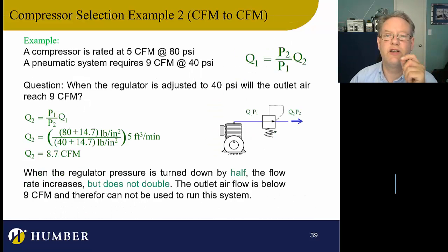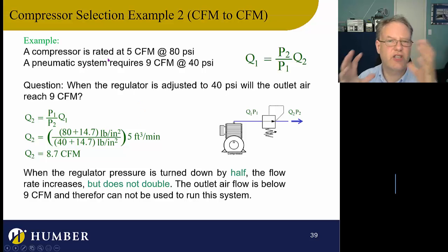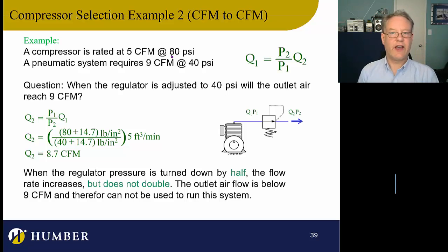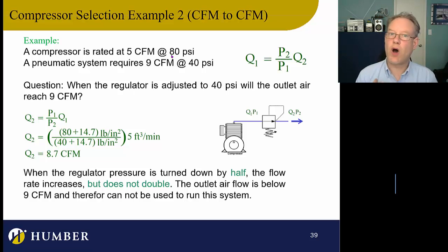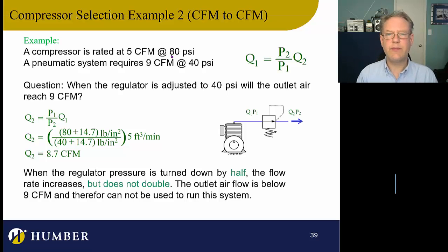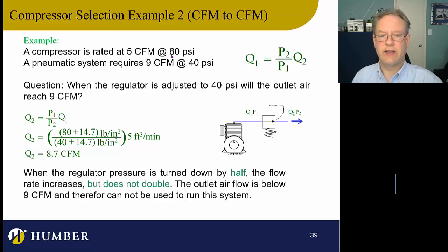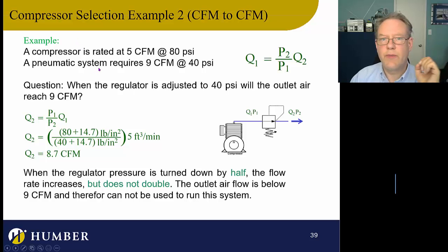Example 2: A compressor is rated at 5 CFM at 80 PSI. The manufacturer says if you set the pressure regulator to 80 PSI, the flow rate will be 5 — because there's a limited amount of power and we're dividing that between flow rate and pressure. But we want this system to run at 40 PSI and we need 9 CFM. Will it work? Just do the math.